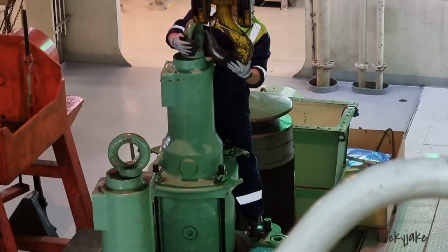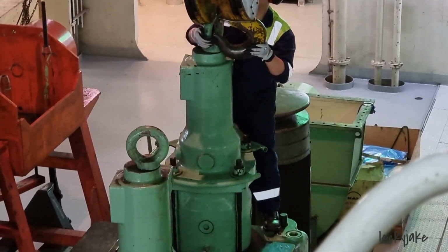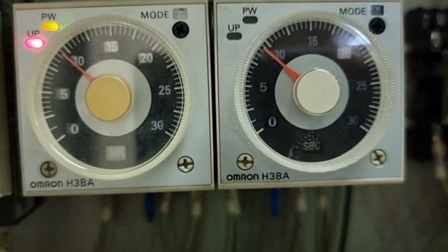Of course, that causes inrush current for the electric motor, which eventually in later time will damage the motor. So they put a timer, set for 1 second or 2 seconds. After he presses up, the timer will be activated before the crane will start running again.